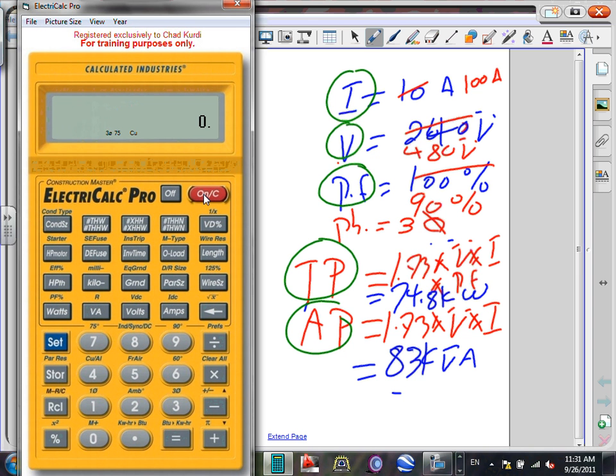You can take any 4 out of these 5 variables and get the fifth. For example, I can put in apparent power, true power, power factor, and voltage and find the current. Or I can put in true power, power factor, voltage, and current to get apparent power. It doesn't matter which one is the fifth. If I know the watts, I input the watts; if I know the volt-amps, I input the volt-amps. If I know the amps and voltage, I can find the power factor - hit set power factor and it'll calculate it.